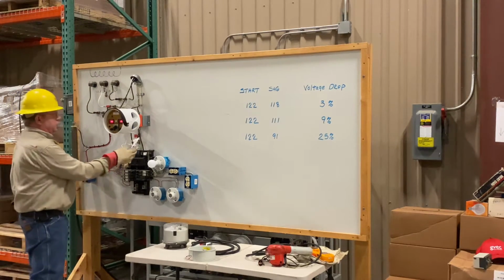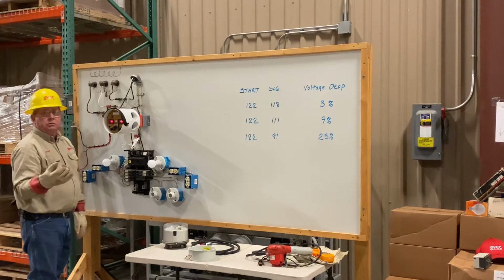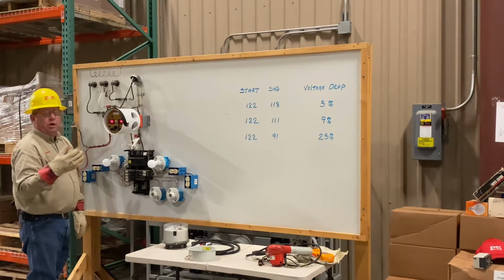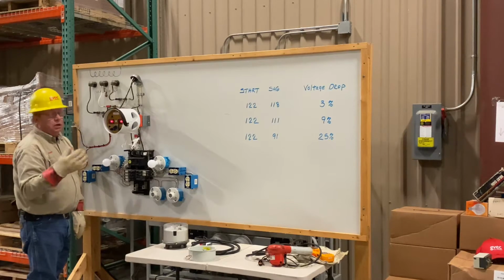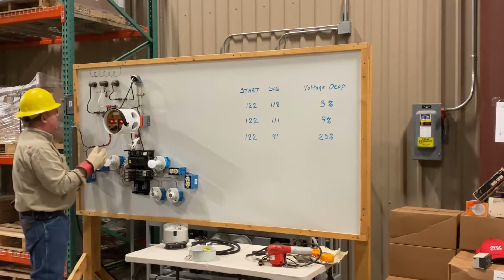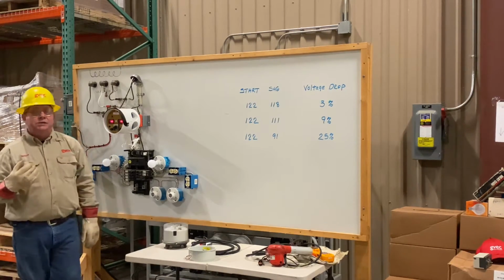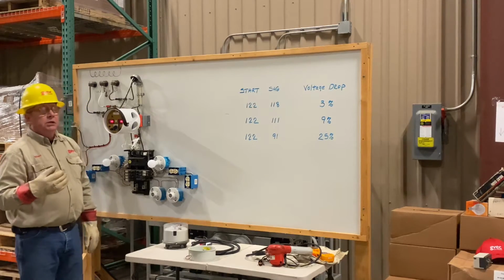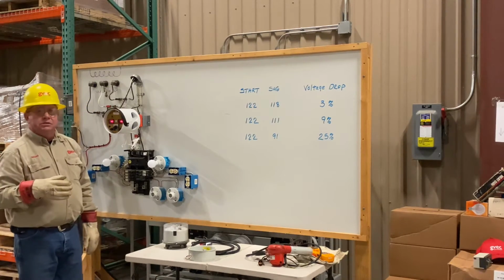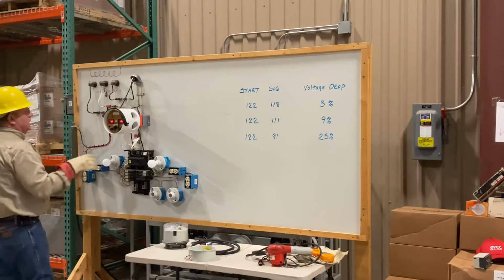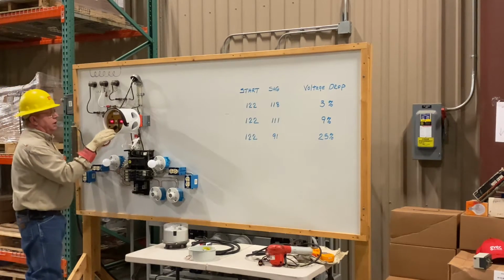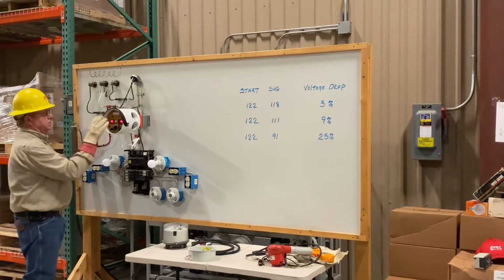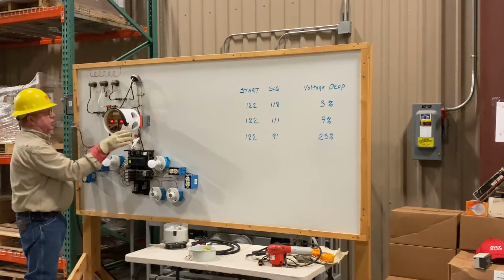Where we connect the neutral determines whether we're on the high side of a bad connector, low side of a bad connector. Right now, I know where the bad connection is. And the bad connection is in the service run to the house. So we're going to take the Super Beast and we're going to add this load to the right-hand side.